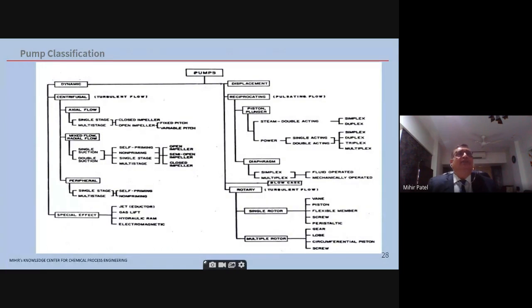On the left, you have the centrifugal pumps, of which again many types are there. At the bottom, you see the special types of pumps: jet, gas lift, hydraulic ram, electromagnetic. On the right-hand side are the positive displacement types of pumps, which again are many types. Diaphragm pumps are in the middle, which have a Teflon diaphragm in the middle, so that protects the non-process part. These are very good, like AODD pumps, air-operated double diaphragm pumps, which are very frequently used for drum unloading, etc. Rotary pumps are there at the bottom: screw pumps, gear pumps. We'll discuss this in detail also.